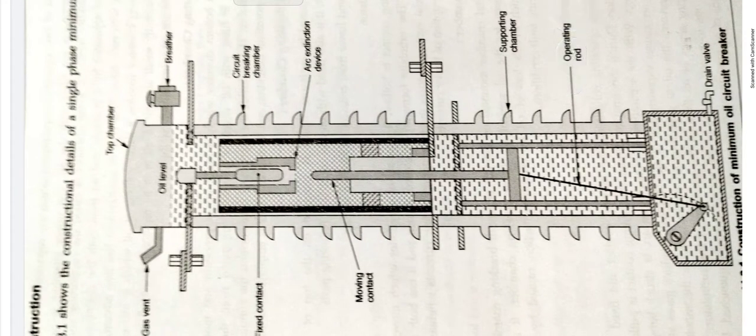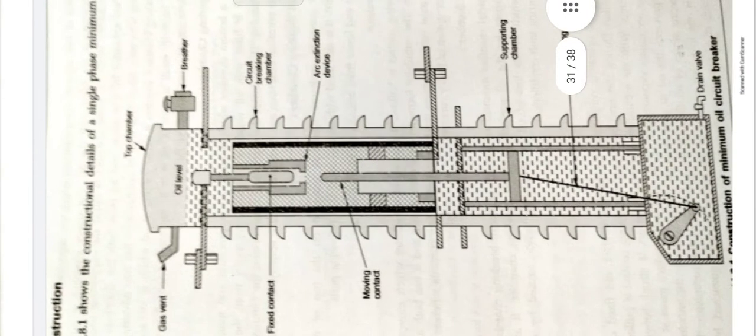Third one is top chamber. It is a metal chamber mounted on the top of circuit breaking chamber. It provides expansion space for the oil present in circuit breaker breaking chamber. It also contains a separator which avoids loss of oil by centrifugal action caused by circuit breaker operation during faulty condition.